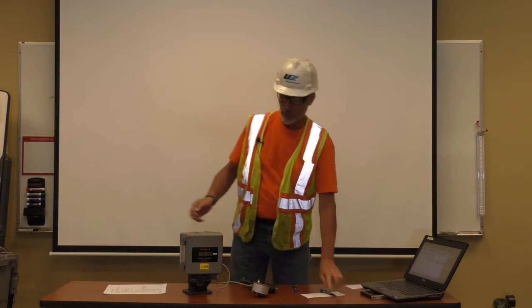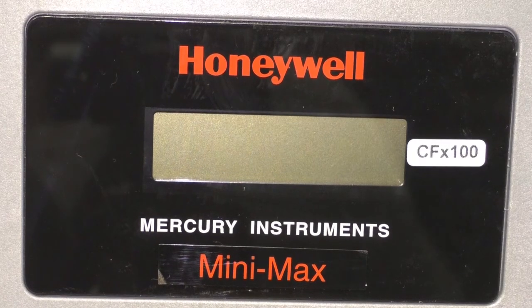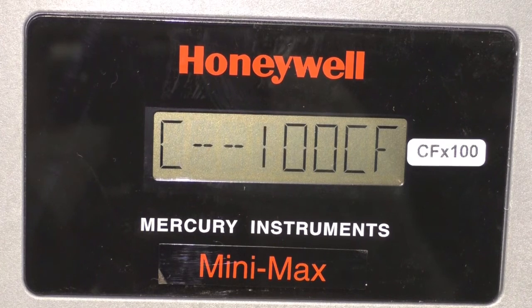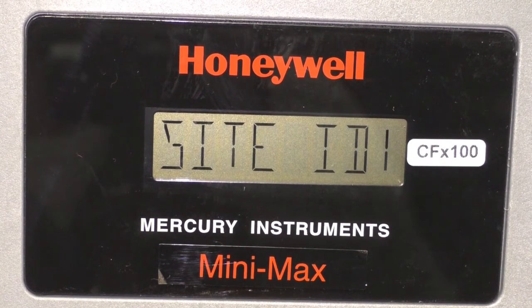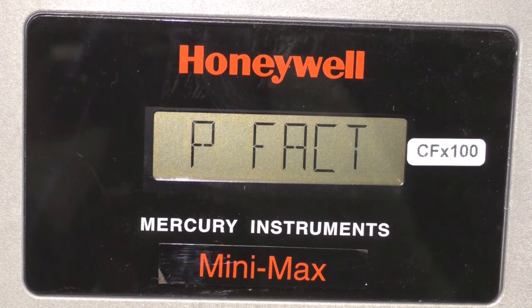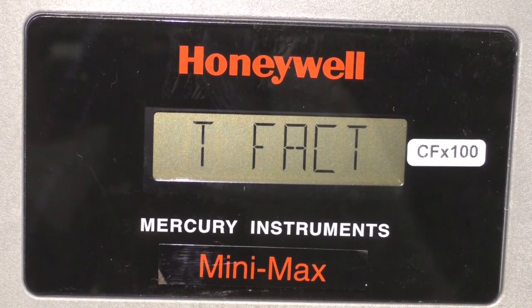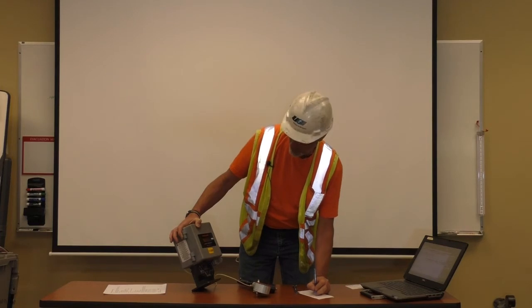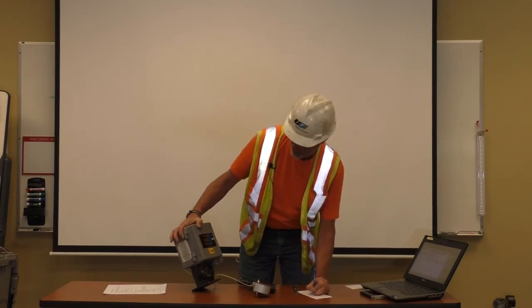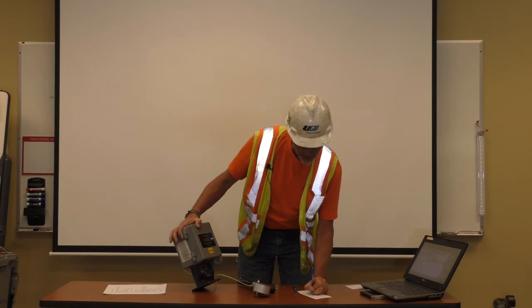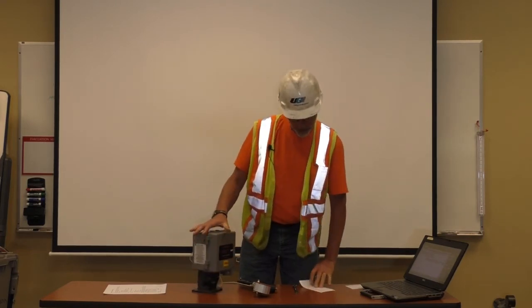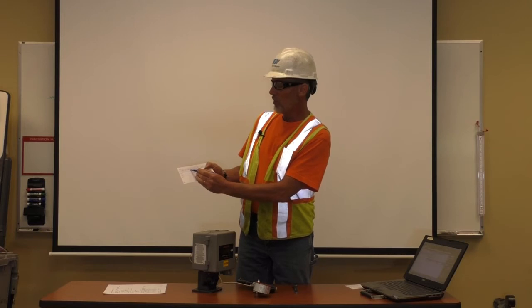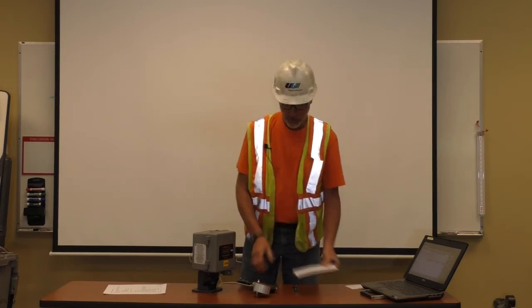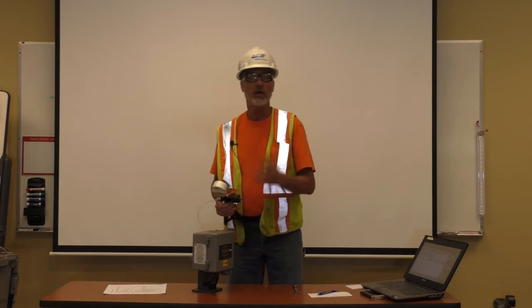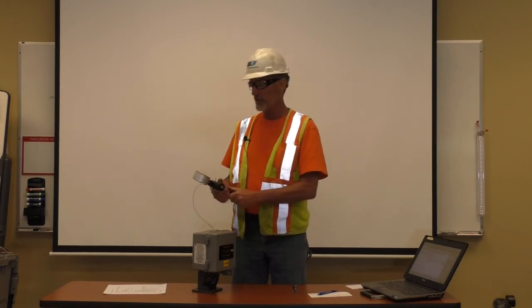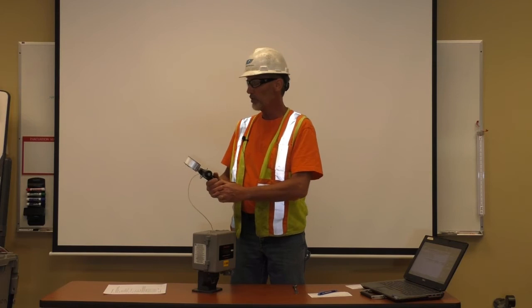The next thing you will do is scroll through your device to get to the total correction factor. For our 20-pound test, it is 2.3568. That goes into your corrector total factor as found. Now we'll do the high end, which is 80 pounds. Anywhere between 75 and 85 is acceptable. We'll increase our pressure.